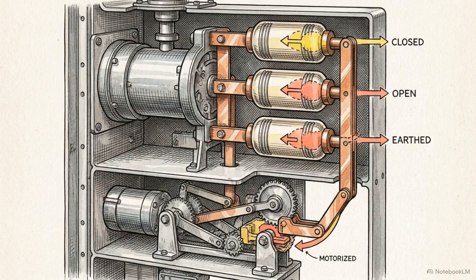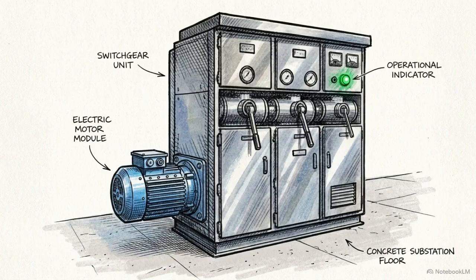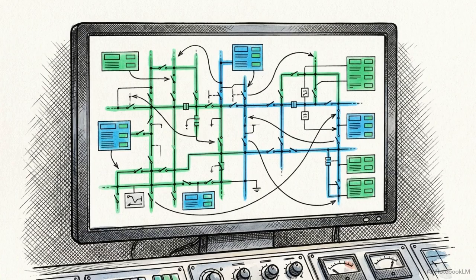Inside the bay, the active switching is handled by fixed vacuum circuit breakers and motorized 3-position switches, physically shifting between open, closed, and earth states. Equipping these switches with motors removes the need for manual intervention on the substation floor. It enables the immediate remote operation capabilities required for an automated smart grid.